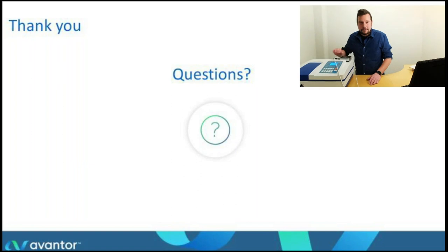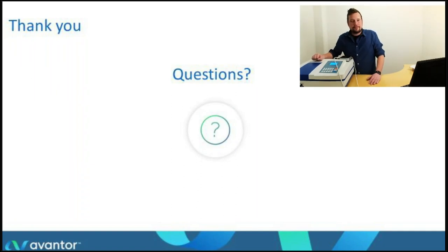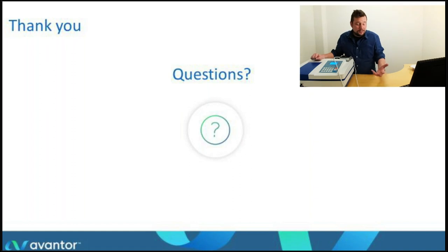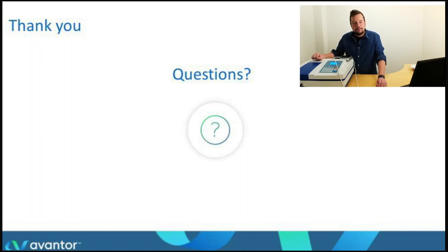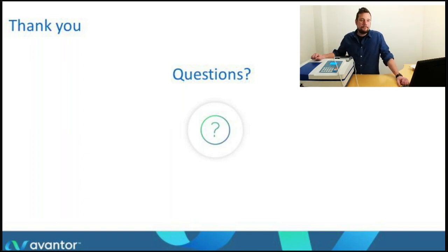Thank you, Emil. I will read out the questions and Emil will try to answer them. The first question is from Murat: 'Is Spectralink suitable for the pharma industry? Is it complying with current regulations?' It does not have FDA compliance as part of the software package, so you cannot use it in a GMP regulated environment. However, we do have pharma companies as customers, but they only use it for research in research laboratories — not for diagnostics, not for GMP environments.